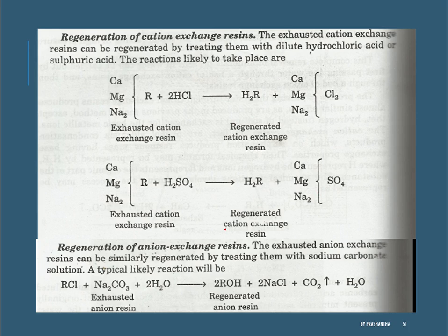If the anion exchanger has to be regenerated, then it is reacted with sodium carbonate. So RCl plus Na2CO3 will react in the presence of water. It forms ROH and NaCl, carbon dioxide is liberated, and water is also generated. So this is the regeneration process. First we saw how it reacts with the hardness in the water. Next, once the resins are exhausted, we have to regenerate them.